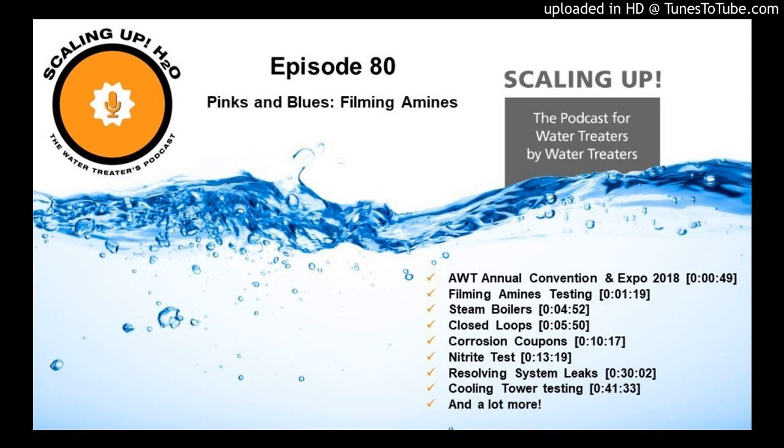So we did that. We came back 2 weeks later. We did have a positive on our Filming Amine test, and we went ahead and put our final 1,500 ppm of our Filming Amine. So folks, we finally did it. It took us 3 months, but we finally got to 3,000 ppm.